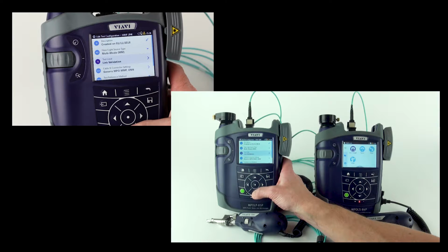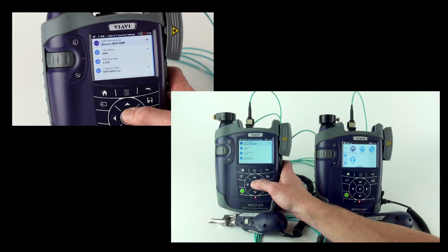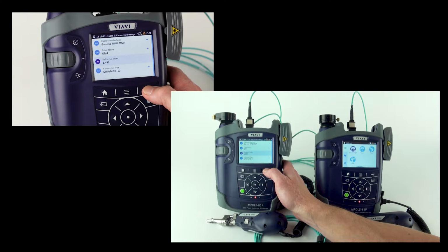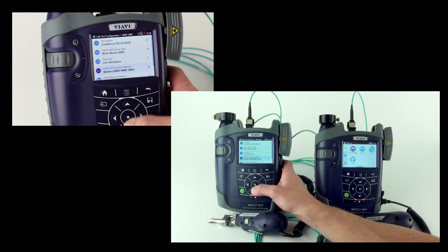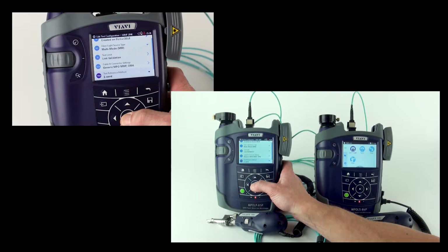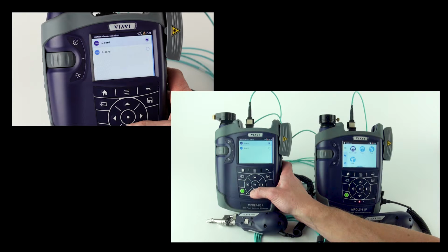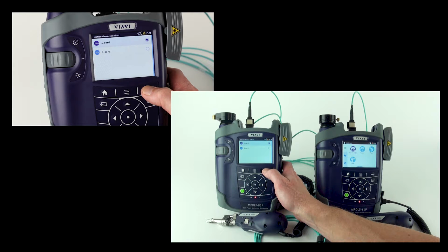I then return back to my test configuration, and I'm able to set up my cable and connectors. So I just chose a generic MPO fiber. I've said that it's OM4, refractive index, which will have an impact on your length measurement, and what your connector type is. The reference method, one-cord reference method, is really the standard one. In some cases you may need to do a three-cord, but with MPO, because of the pin-to-unpin, doing a two-cord is really not possible.